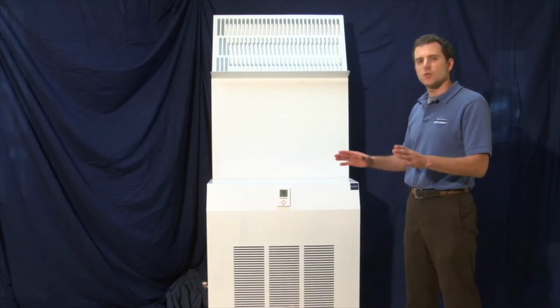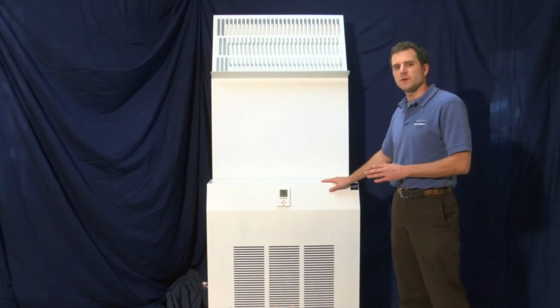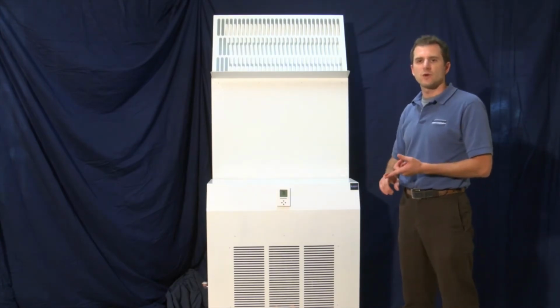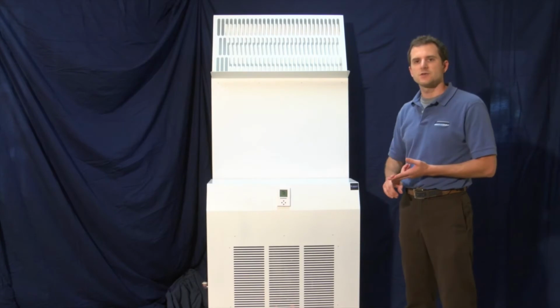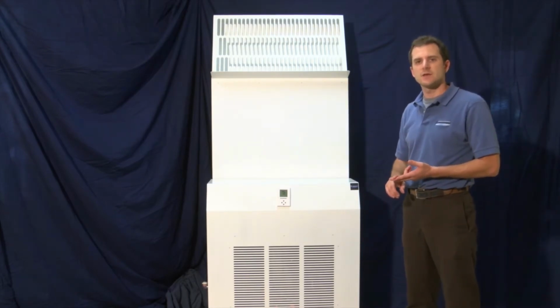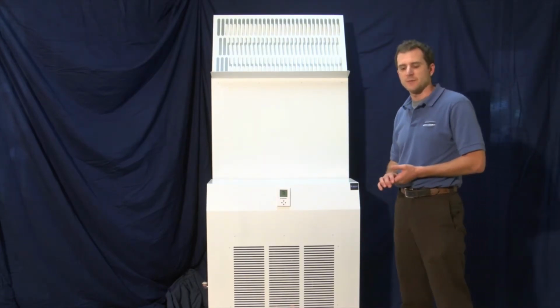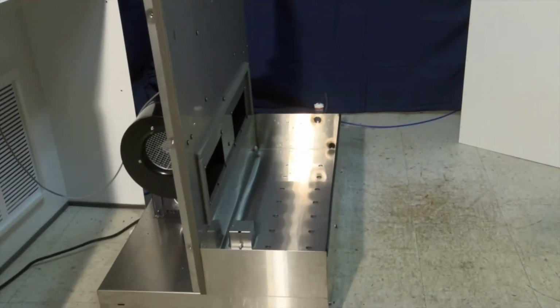An undersized water treatment system can starve the humidifier for water and not allow it to work correctly, and even in some scenarios damage the transducers because they're not allowed to operate with the proper amount of water on top of them. The best practice for ensuring the longest lifespan out of your transducers is to keep the water pan clean and clear of any contaminants. The transducers are small, crystallized discs vibrating at an ultrasonic frequency. A transducer should last 10,000 hours, or about 3 years under nominal conditions.